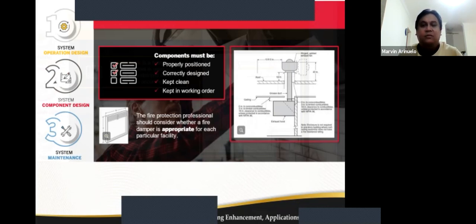A fire damper, so what is that? It is placed normally in a hood at the duct connection to prevent the fire from getting into the ductwork. And it is also a form of passive fire protection system. The fire professional should consider whether the fire damper is appropriate for each particular facility. Grease extraction and control devices must be placed properly and should be emptied at the end of each rush period to avoid an extra fuel source in case of a fire.